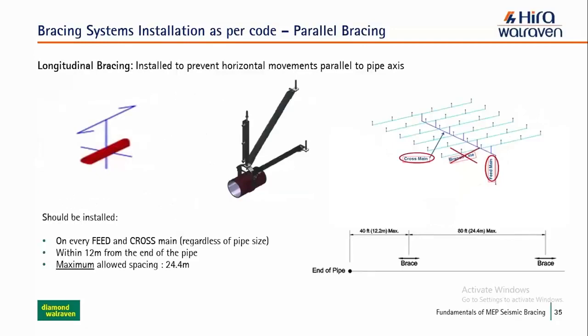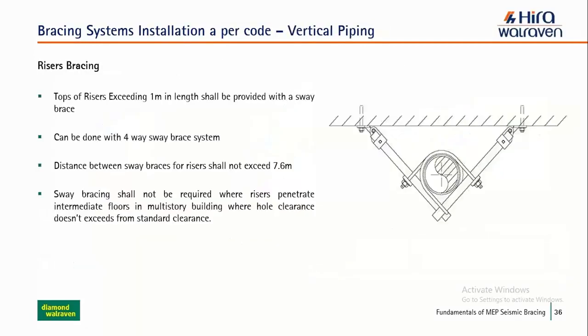This is for the horizontal run, 12.2 and 24.4. In vertical risers we have 7.6. The support or span should not exceed 7.6 meter. Sway bracing shall not be required where risers penetrate, because risers sometimes penetrate through the ceiling, through the structure, and then they have no chance for movement. That needs to be considered while designing any riser bracing system.